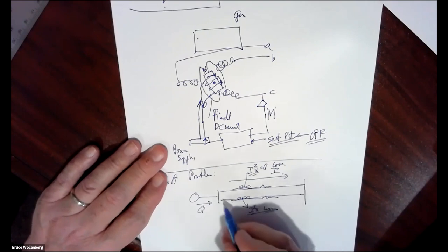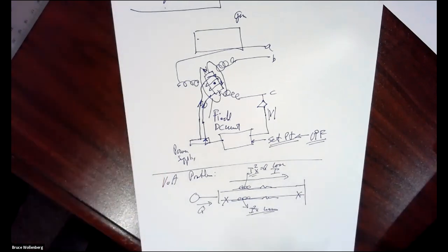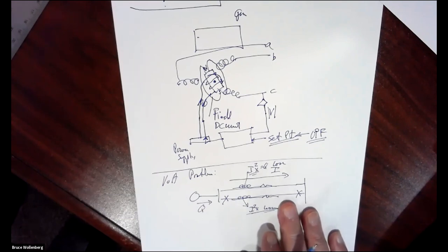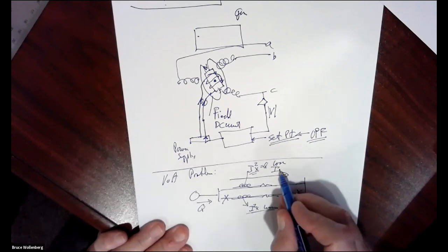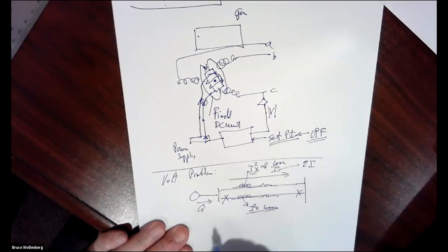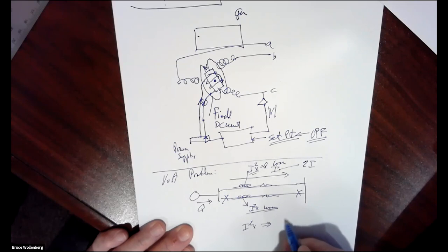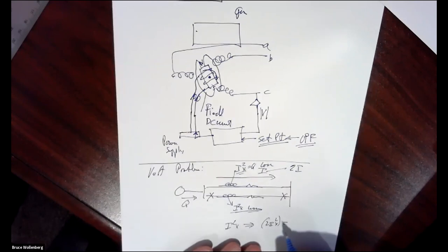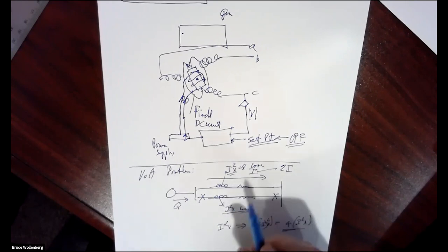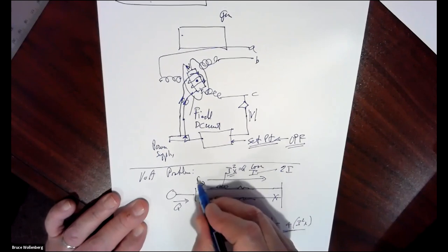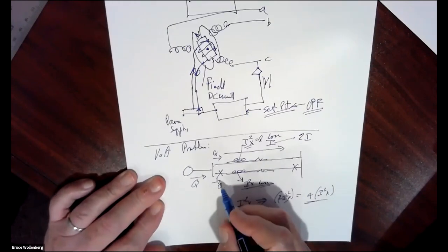Okay, now all of a sudden we lose this line. Again, insulator fails, mechanical failure, whatever. The line goes out. Well, now this line's current becomes 2I, roughly, and now the I squared X goes to (2I) squared X. So that becomes 4 times I squared X. So suddenly I need 4 times the amount. Before, I was supplying Q, and now that's 2Q.